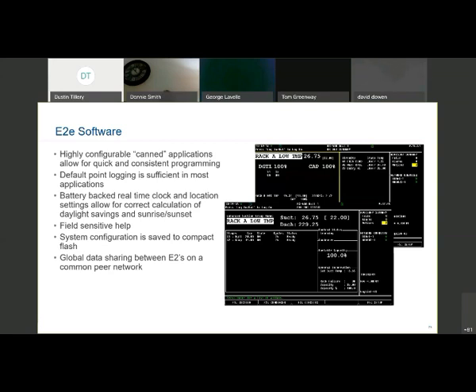It also has default point logging, sufficient in most cases, but if you have a customer that wants more data, you have the ability to go in and add or delete those logs as needed. There's a battery-backed real-time clock and location settings in the E2 itself that allow things like sunrise and sunset times and daylight savings time to be automatically set based on your location. And then there's field-sensitive help.